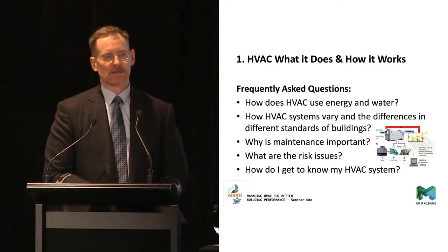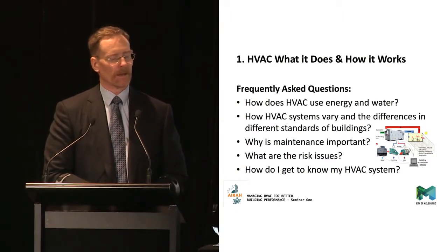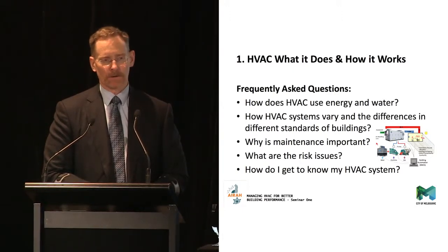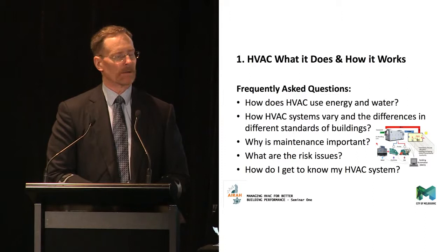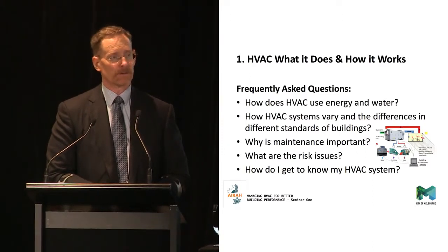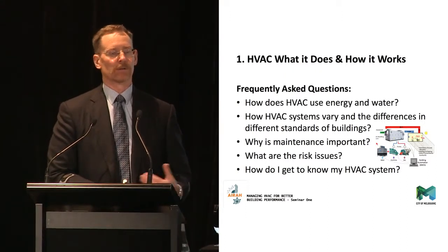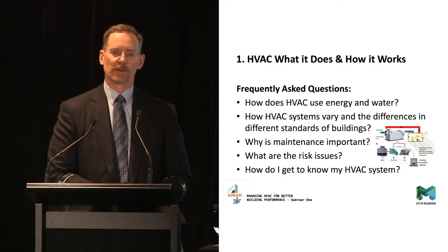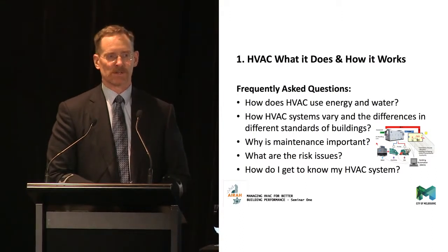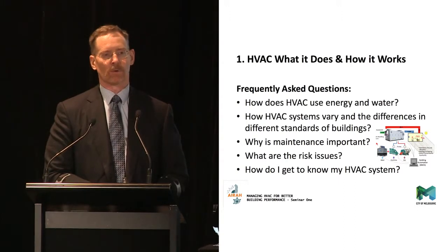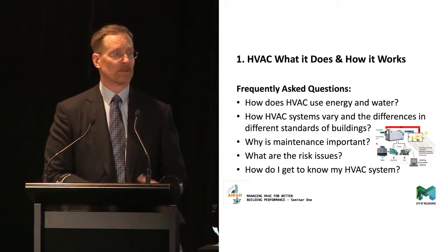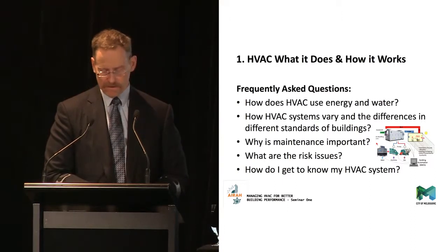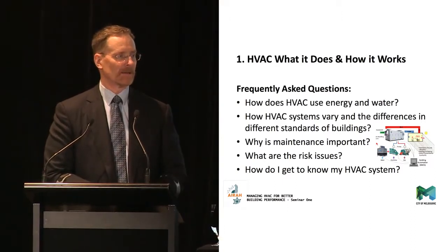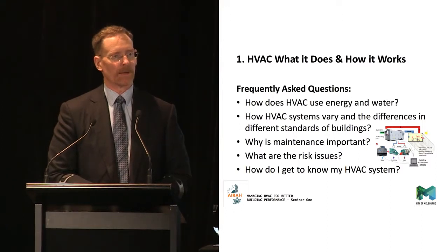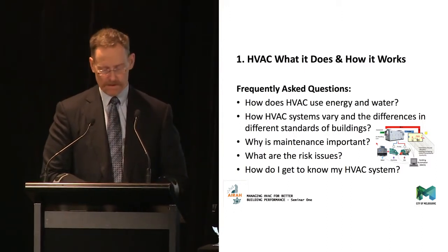On the other side, air conditioning systems are very resilient systems the way they're designed. You can have a lot of things go wrong with an air conditioning system which might significantly compromise its age, things might wear out much quicker, you might use a lot more energy - you can have a lot go wrong and never notice because it'll still maintain conditions. It'll still be 21 degrees inside, but you're using twice as much energy and you'll never know. Or you're wearing out your chiller at twice the rate you should be, but you'll never know just because the thing's still doing its job. There might not be enough outside air coming in - it's a long time before people start talking about it being a bit stuffy, so you're outside of regulations.